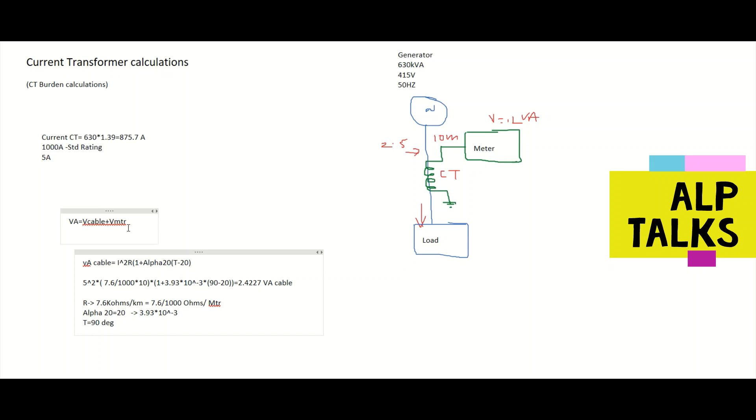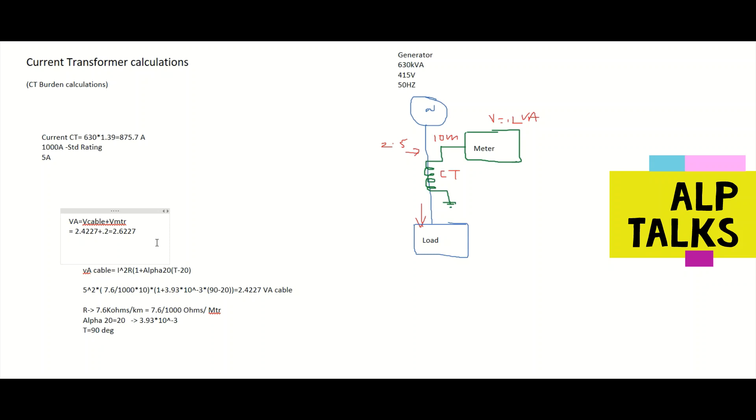So what is the burden now? So now we calculated 2.4227. Already we have 0.2 VA for the meter burden. So together we'll get 2.6227. So we will take standard burden of 5 VA.